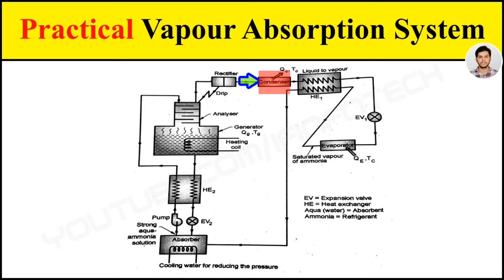If the water particles are not completely removed, they will enter the expansion valve where they freeze and choke up the pipeline. The strong ammonia vapor passes through the condenser where it is cooled and changes phase, rejecting the latent heat to the cooling water.